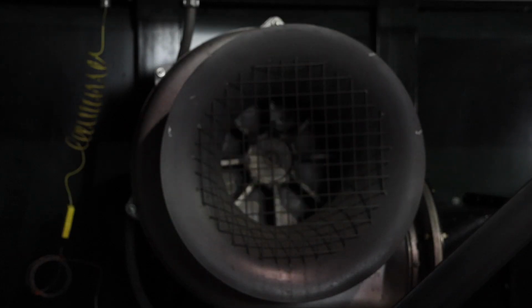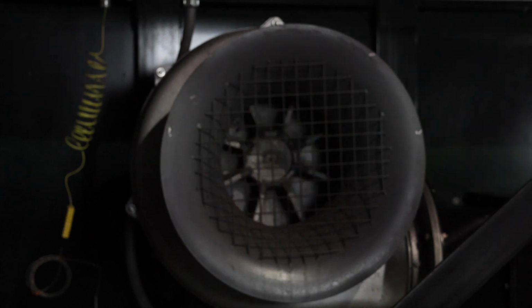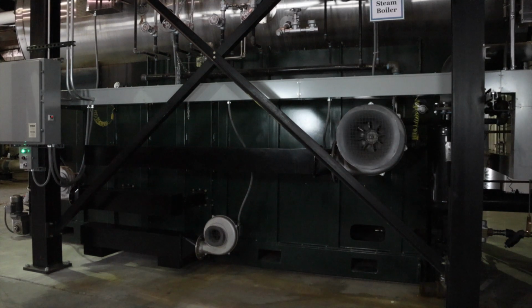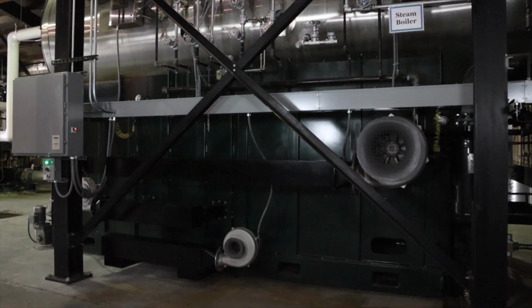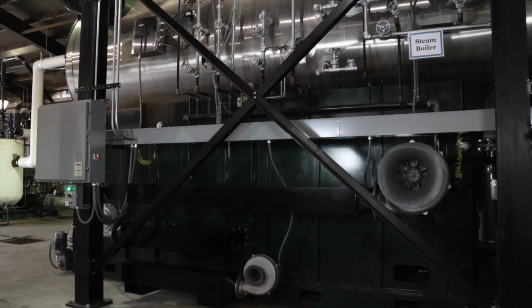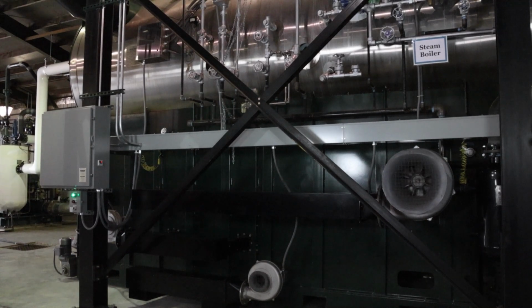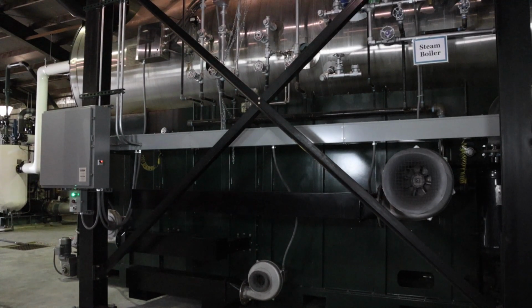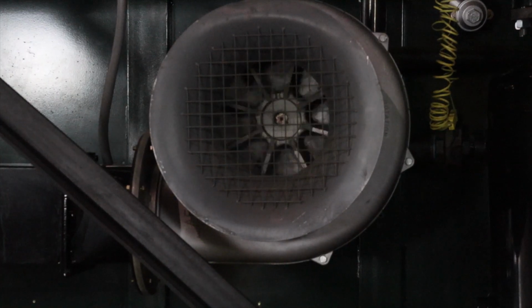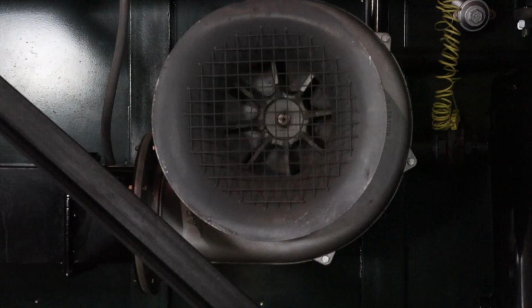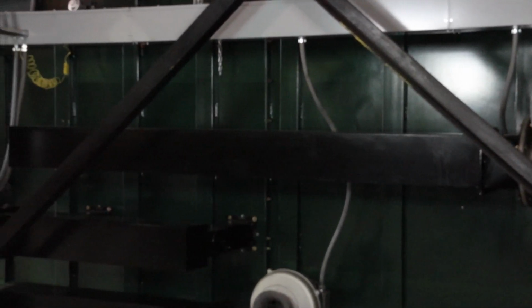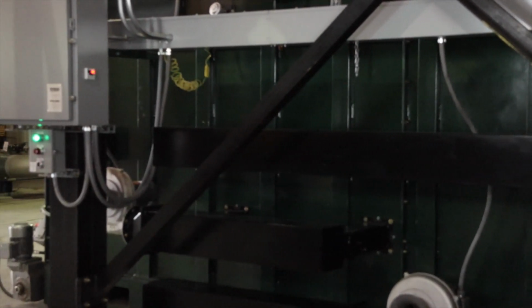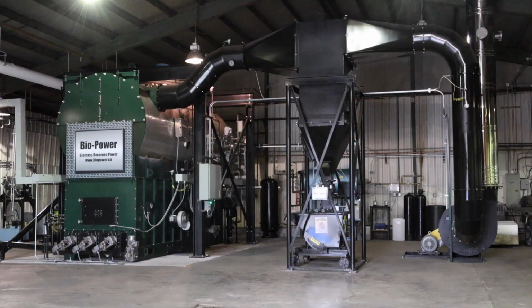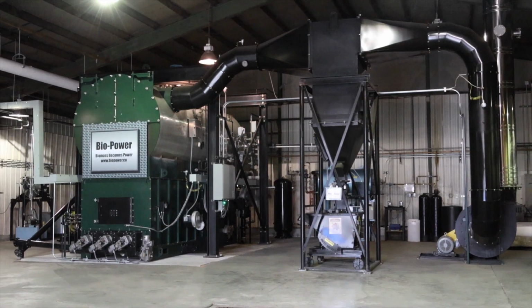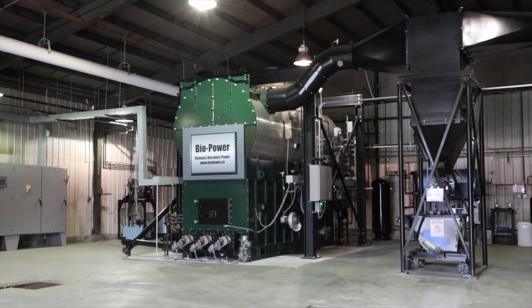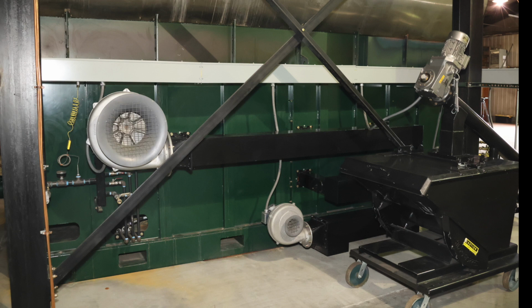The combustion air for the process is provided by 3 separate sets of combustion fans at 3 levels of the combustion chamber: the primary, or under fire combustion air, the secondary combustion air, and the tertiary, or over fire combustion air. The combustion fans are also on a variable frequency drive. By adjusting the speed of the individual fans, we are able to compensate for lower quality fuels or fuel with higher moisture content.